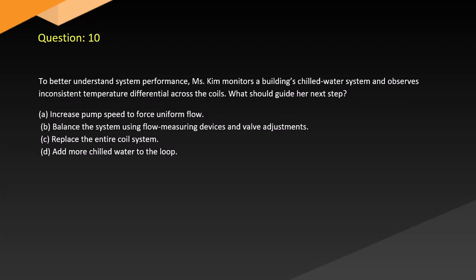Question 10. To better understand system performance, Kim monitors a building's chilled water system and observes inconsistent temperature differential across the coils. What should guide her next step? A. Increase pump speed to force uniform flow. B. Balance the system using flow measuring devices and valve adjustments. C. Replace the entire coil system. D. Add more chilled water to the loop.